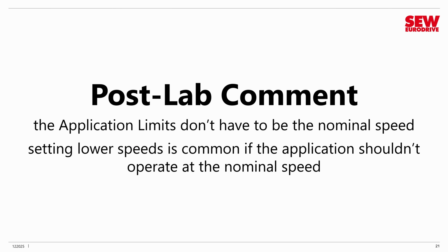Walkthrough is over. Before we wrap up this lab, I want to give a post-lab comment. In this lab, you set the application limits in order to control what the motor could and couldn't do, and we set it to the motor's nominal speed. But you don't have to do this. In real life, it is perfectly fine to set a lower speed for the application limit. You can do this if the application should never run at the motor's nominal speed. Maybe it would only run safely at a lower speed. In that case, set the application limit to that speed instead, and that will protect your application. So just a handy little tip.